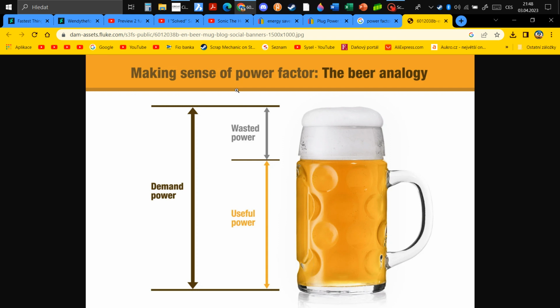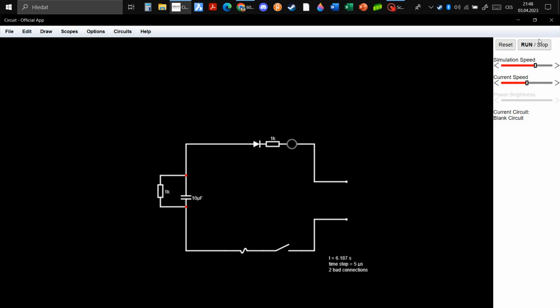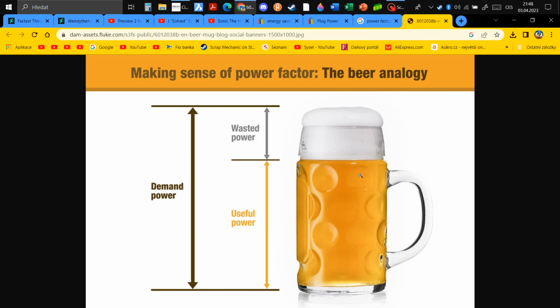To make a device work, they're relying on power factor correction, which is real. By putting a capacitor, which you can see inside the product — there's a big old 10 microfarad motor start capacitor — that capacitor gets rid of most of this wasted power, reducing the ineffective power draw, meaning the device will cost less to run.